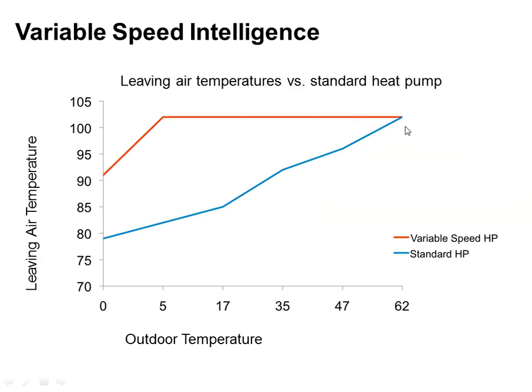Whereas this red line represents what we do on the variable speed heat pumps, which is we target like 104 degrees, say. We try to maintain that for as long as possible. So as the temperature drops outside, we continue to keep the discharge air temperature high. And the way we do that is by slowing down the indoor fan blower. So we continue to ramp up the outdoor condensing unit's capacity as we slow down the indoor blower speed. If we move air across the indoor coil slower, it'll have more time to pick up the heat that we're pushing into it, and hence a higher discharge air temperature.